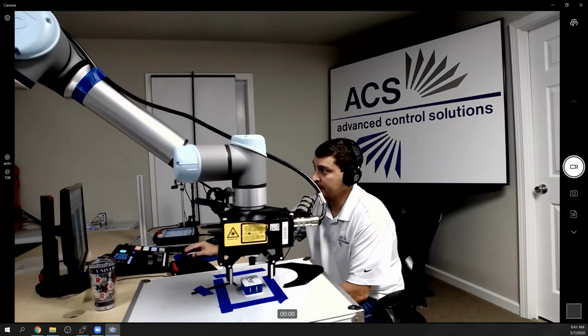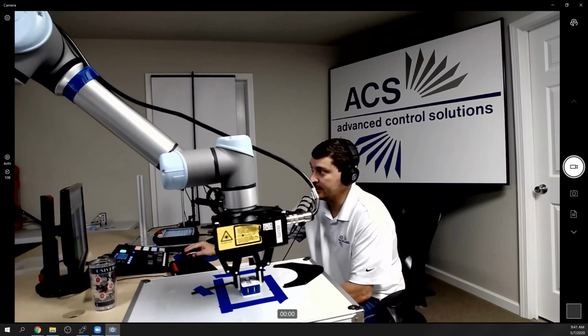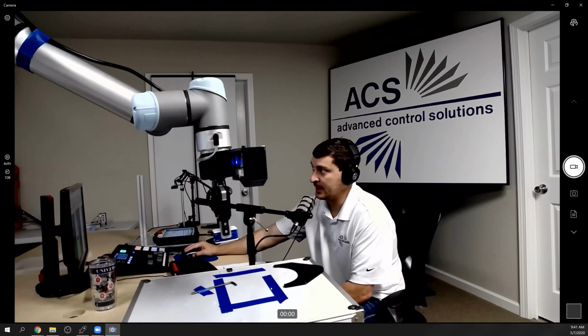It can handle some angular orientation there too. Now, I would slow it down for you, but the one caveat of this is the speed at which you calibrate needs to be the speed at which you scan, so the calibration is valid, because it's not using an encoder, it's using a time base.